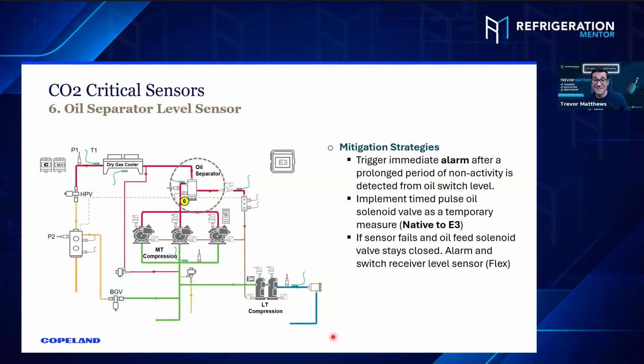Yeah, the timing sequence, and we've got high pressure oil separators coming online now. We've got 20-second fill rates, 120-second fill rates. There are different size orifices. A lot of people don't know, oh, it looks the same, it's an OM3 or an OM5 or OM8, but inside it's got a different orifice. So it feeds a different amount of oil when it opens up. High pressure versus low pressure is going to be different. Absolutely, that's been fun.